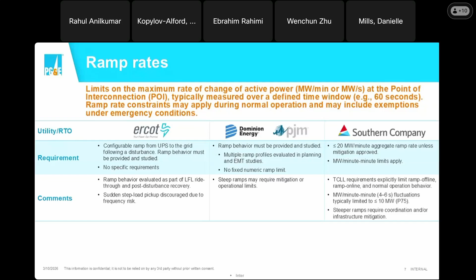Just deep diving a little bit into what these requirements look like. Over here, there is an instantaneous step change limit, and there's also a sustained ramp rate limit over a defined interval. So ATC, for example, has a limit where you must limit the amount of repetitive active power changes to within 25 megawatts over a 5-second rolling or sliding window interval. Then any active power change greater than 50 megawatts must be limited to less than 0.5, so that's the ramp limit that they want you to take, which is 0.5 megawatts per second. And there are some plots at the very end as well that do more justice to this than my explanation. But I think the key intention here is to tell you that these are all of the different flavors in which these requirements are taking shape.